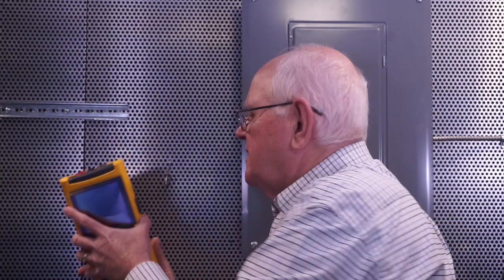So in that case, what I might want to do is take another type of test equipment, and now with my motor online and energized, I'm going to do some enhanced testing. Now I can do some power quality checks on my motor. Find out that maybe I need to put some types of filters on my variable speed drive, or get a different type of motor with different types of winding that's rated for that drive, so that I don't destroy the insulation as I get spikes and different power quality issues out of that drive for that motor. So these are examples of different types of testing that I can do, all talked about in NFPA 70B.